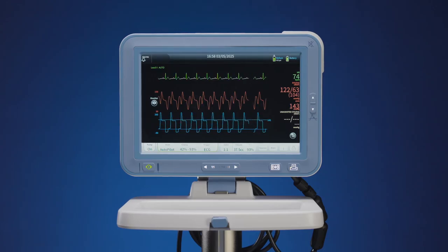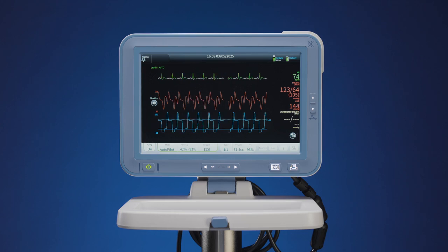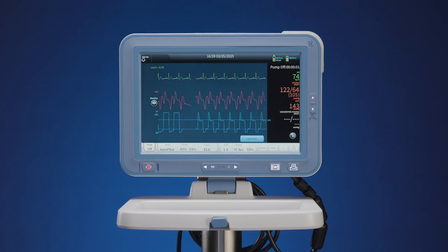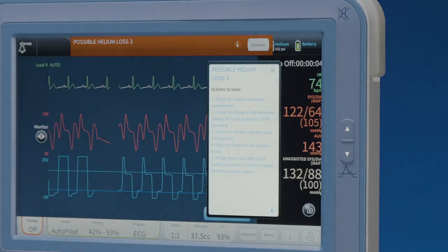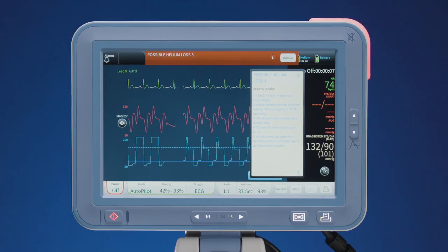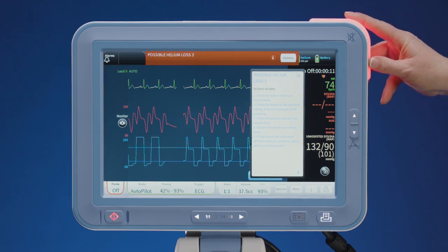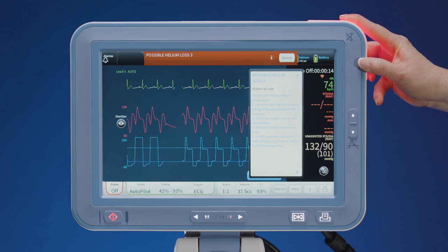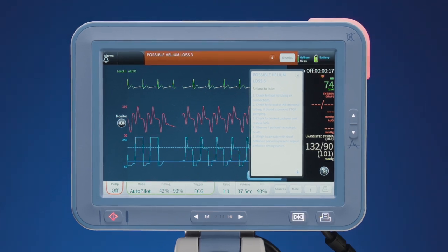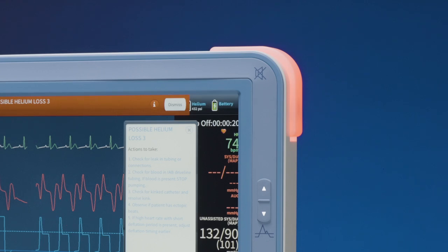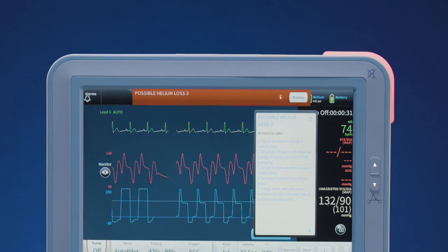The AC3 Optimus IABP diagnostic alarm system continuously monitors operating conditions and will detect and alert the user to conditions which require a response. When an alarm condition occurs, the screen displays an alarm message, including suggested corrective actions and additional help if needed. The upper right corner of the display control head is the corner switch and the alarm silence key. The key also provides a visual indication that the pump is alarming and the severity of the alarm. The corner switch will light red for high-priority alarms, yellow for medium-priority alarms, and blue for low-priority alarms and alerts. An alarm banner will also appear on the top of the control display screen in the matching color of the priority.